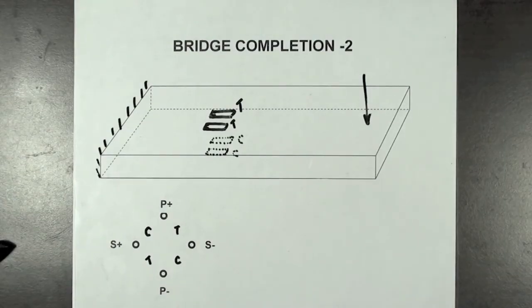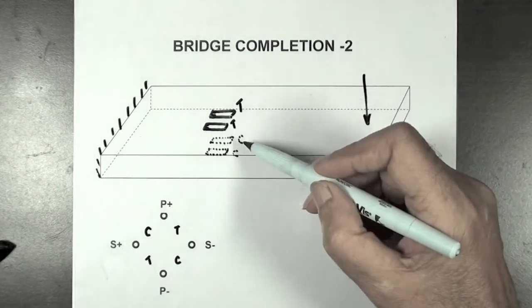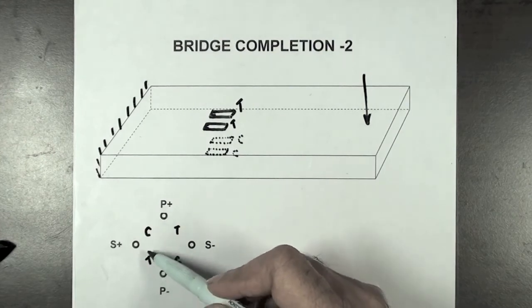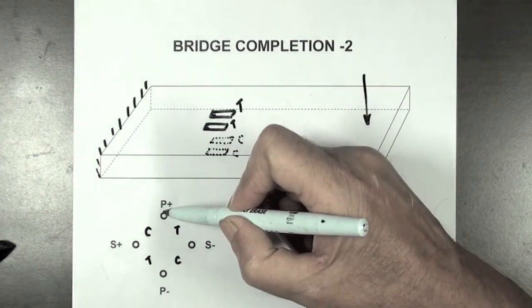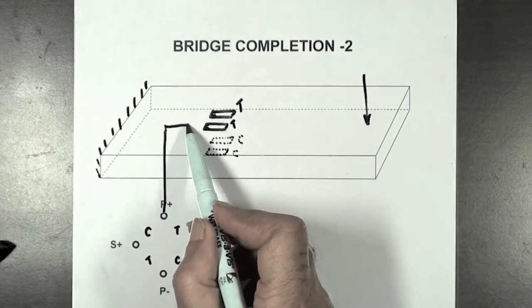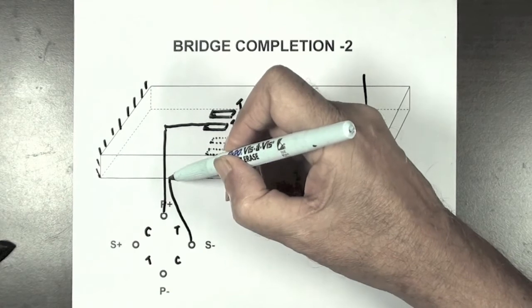With four strain gauges on the same beam—two on the top surface and two on the bottom surface—when the beam is subjected to bending, the two top gauges will be in tension and the two bottom gauges will be in compression. These gauges have to be connected together so that a tension gauge is adjacent to a compression gauge in order to get the maximum output from the completed Wheatstone bridge.